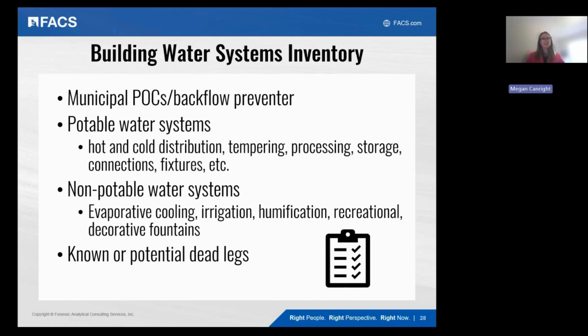With that information, you can start your building water systems inventory, which helps guide the areas you walk through in the building. You want to know where the municipal points of entry and connections are, where backflow preventers are located, how many water systems there are, whether hot and cold systems exist, whether there are multiple hot water loops or subordinate return loops, how water is tempered and processed, how it's stored, and what fixtures and connections are present.